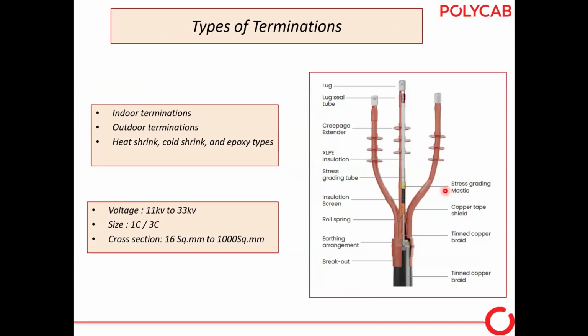Now, let's see the termination parts. Generally, termination has two types: indoor termination and outdoor termination. In old days, epoxy type terminations were used, but nowadays no one is using epoxy type termination; heat shrink terminations and cold shrink terminations are there. Another is touch proof or screen terminations for RMU or GIS termination. The voltage range is 11 kV to 33 kV, single core or three core, and cross section 16 square mm to 1000 square mm.